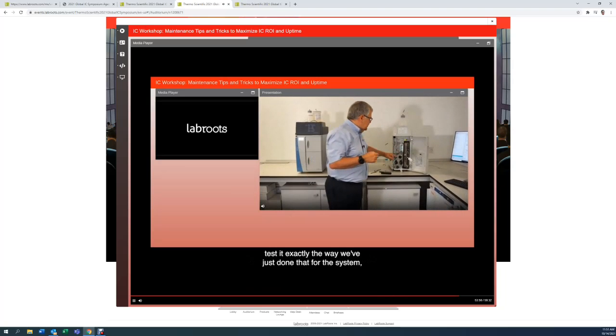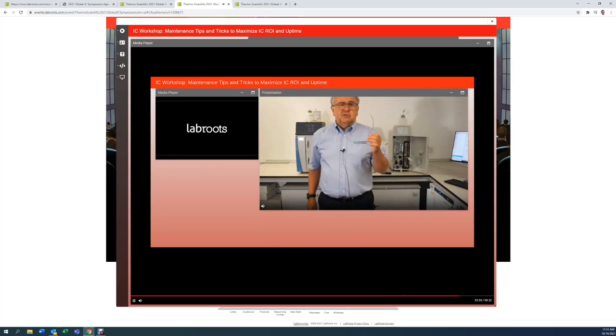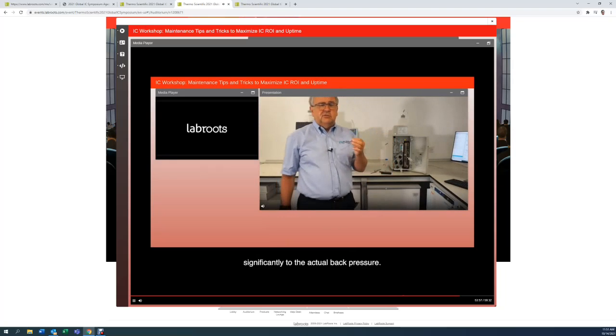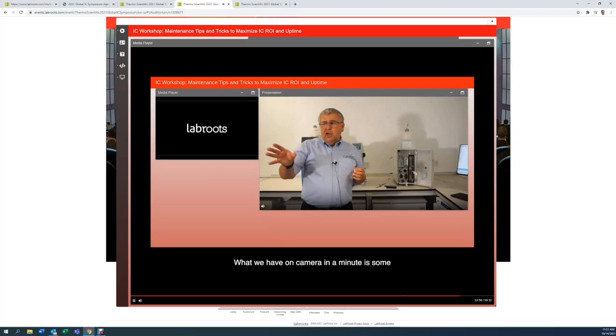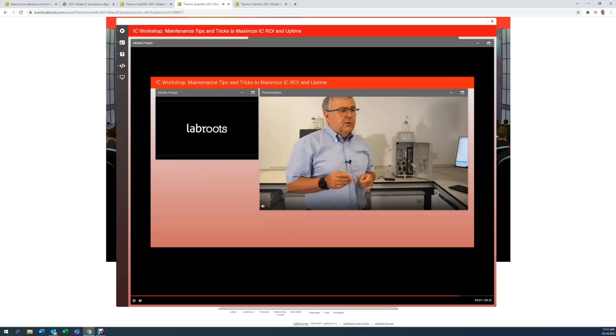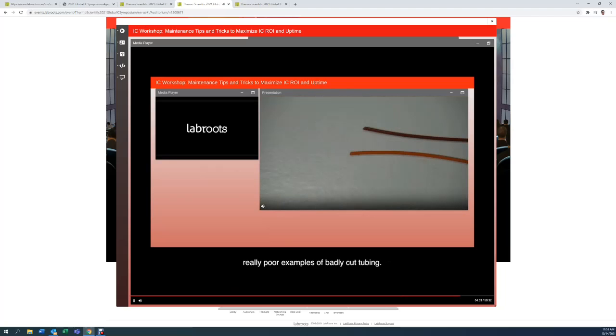we've just done that to the system. Connect it in and make sure it doesn't contribute significantly to the actual back pressure. What we have on camera in a minute is some really poor examples of badly cut tubing. Now, this is tubing which is cut with effectively a pair of scissors. As an engineer, we have on occasions gone out to customer sites who have basically not used their tubing cutters and have used basically scissors to cut the tubing.